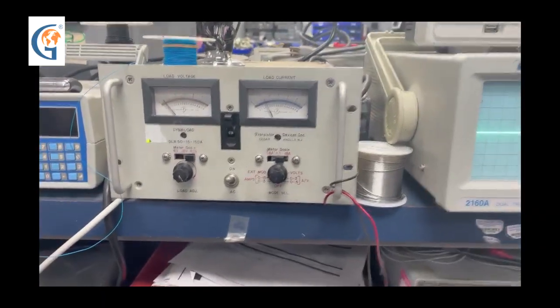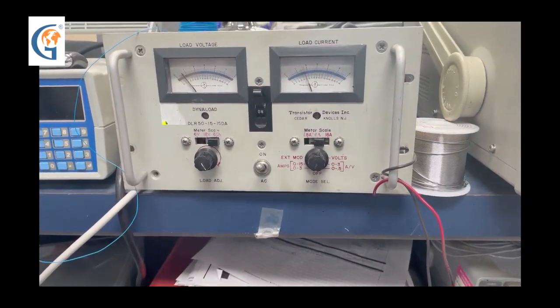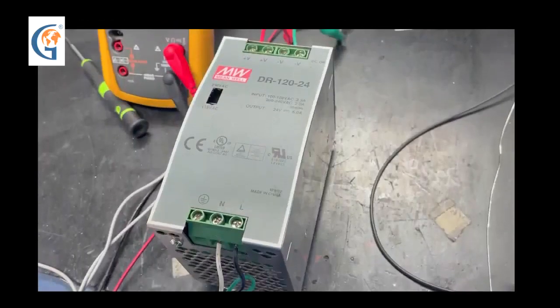This problem we can only detect because we tested under a full load. Just checking the voltage showed the supply to be good.